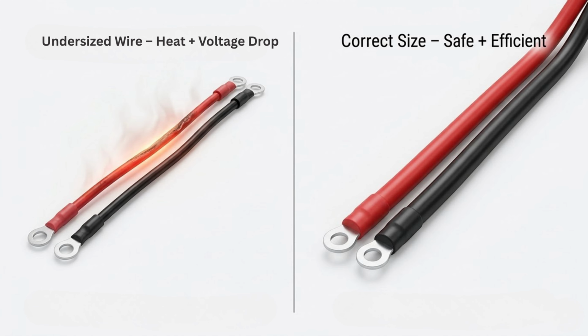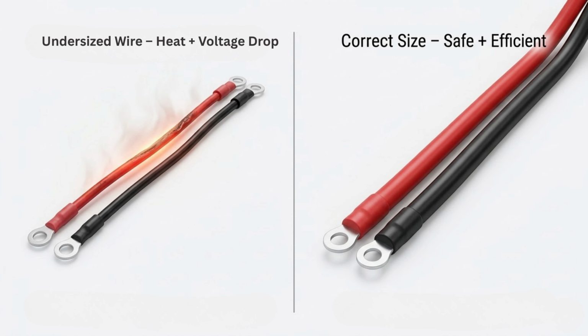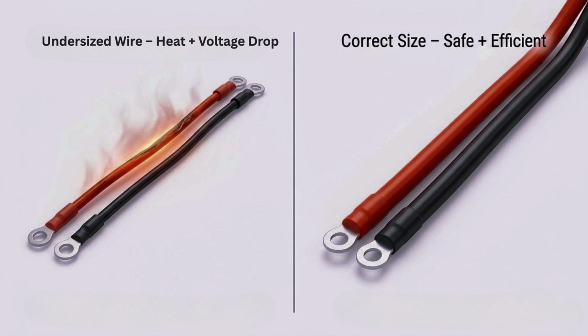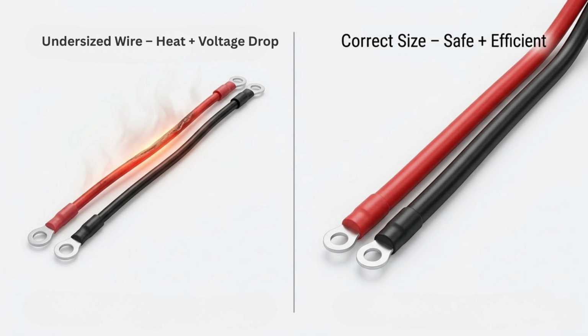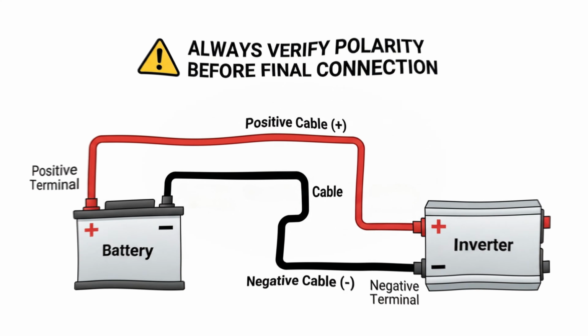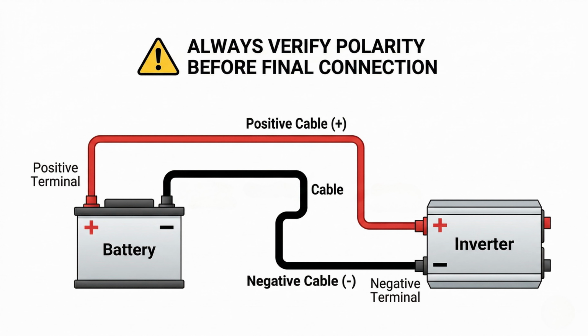This is one of the most common DIY lithium battery wiring mistakes, and it is also one of the easiest to underestimate. A lot of people look at a cable and think, that looks thick enough. But in off-grid electrical systems, looks mean nothing. The numbers are what matter. Lithium systems can push high current through cables for extended periods. If the cable is too small, resistance increases. That creates heat, wastes energy, and can lead to performance issues under load. You may notice cables getting warm, you may see voltage drop, you may even have an inverter throwing errors even though the battery bank is fully charged.